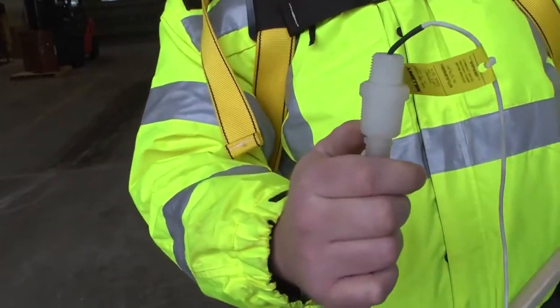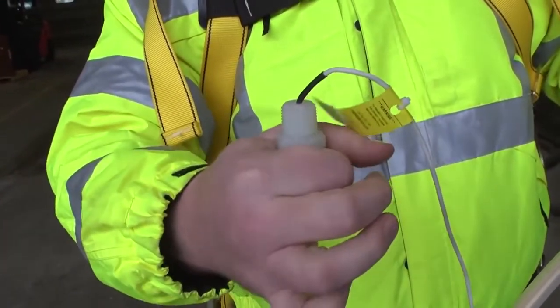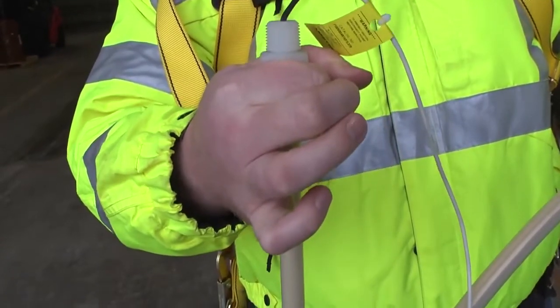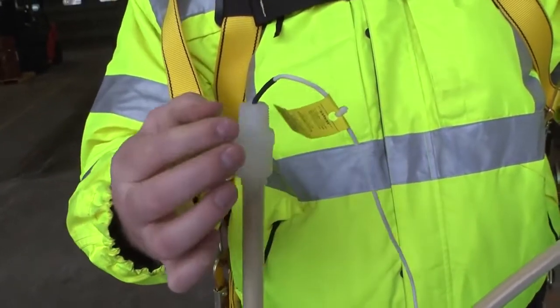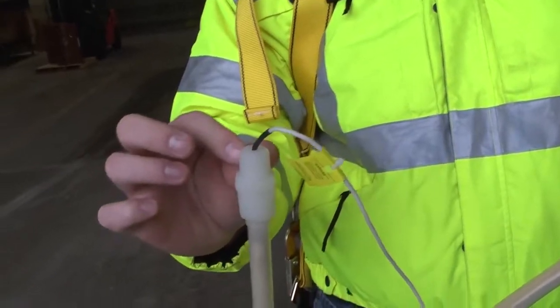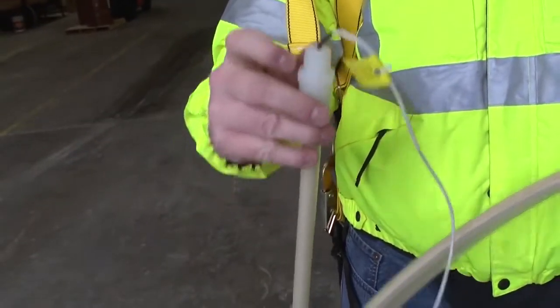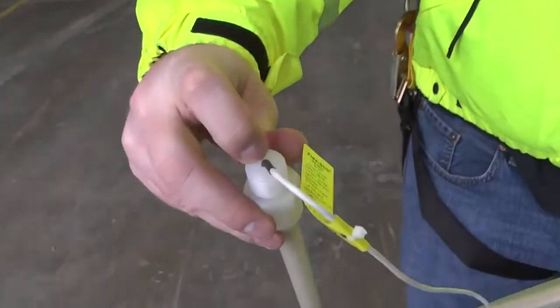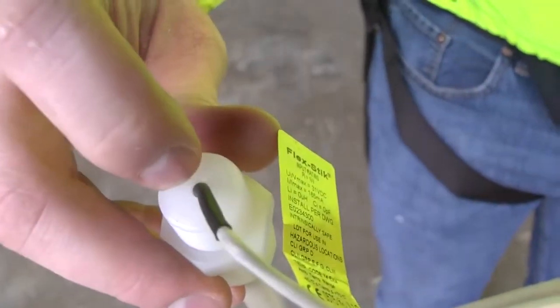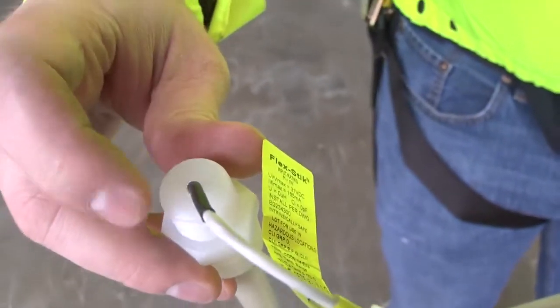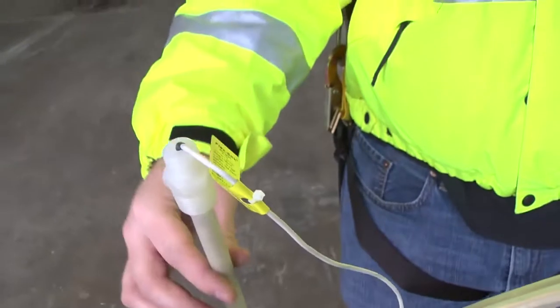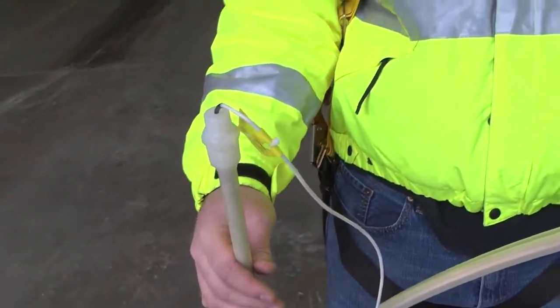So you have this 3/4 inch connector here. You want to make sure that you have a coupler that supports it in the tank. And then you want to make sure you put a junction box over top of this opening here, because this isn't sealed in the top of this probe. And if you go ahead and get water in there, it'll actually cause the probe to short out, and it'll corrode over a period of time, and you have to replace the probe.